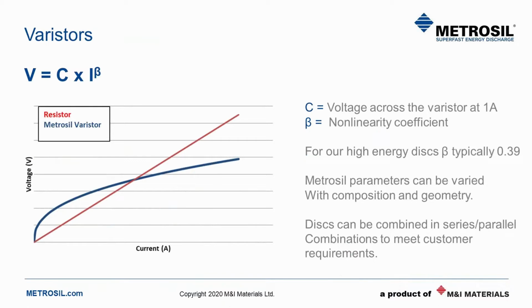METROSIL varistors do not have a fixed resistance, so they do not follow Ohm's law. This is what we mean when we say they're non-linear resistors. Instead, we use this equation: V equals C times I to the power of beta, where C and beta are characteristic parameters of the METROSIL. C is the voltage across the varistor at 1 amp, and beta is the non-linearity coefficient. For our high energy disks, this value is typically around 0.39.